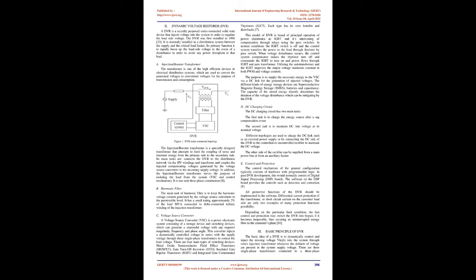The DVR is a power quality device which can protect these industries against the bulk of these disturbances, i.e., voltage sags and swells related to remote system faults. A DVR compensates for these voltage excursions, provided that the supply grid does not get disconnected entirely through breaker trips.